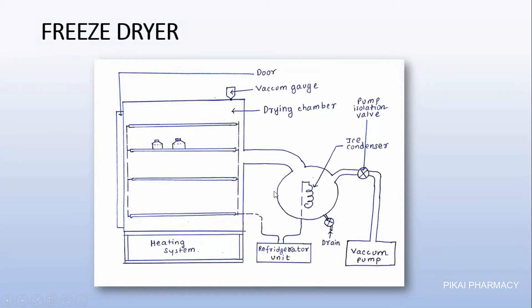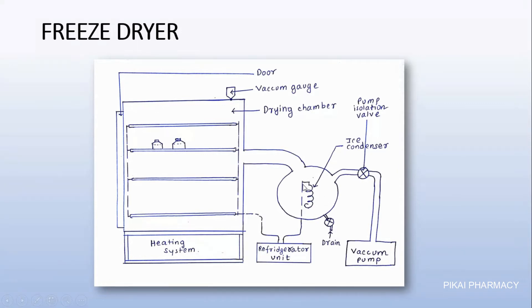First we decrease the temperature using the refrigerant unit to minus 20 degrees centigrade, converting all moisture content inside the sample to ice. Then we turn on the vacuum pump, which decreases the pressure inside the drying chamber. When heat is applied at low pressure and temperature is increased, it causes sublimation. The ice at the surface of our sample gets sublimized to vapor — converted from solid ice to vapor state. This vapor is collected in the ice condenser where it is again converted back into ice.